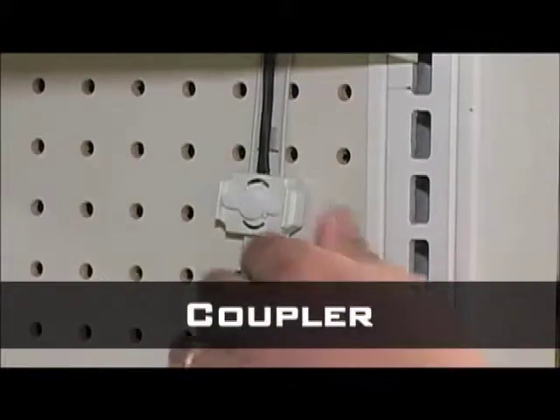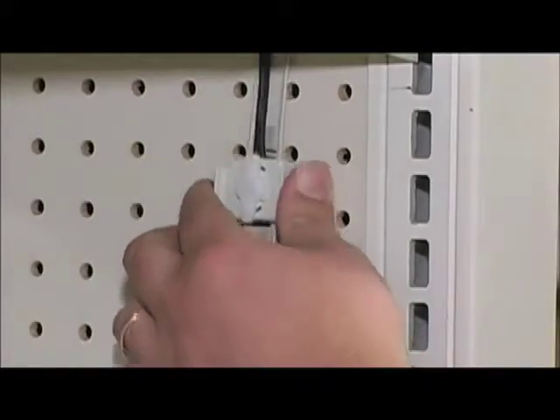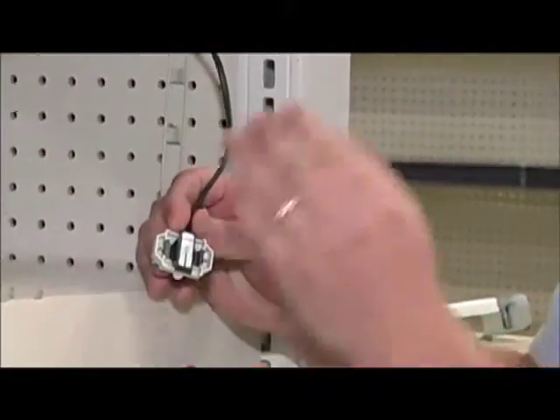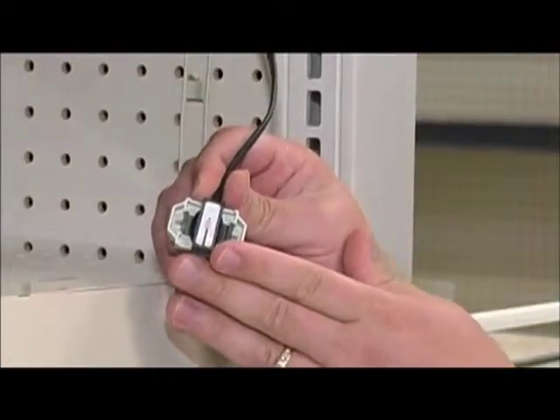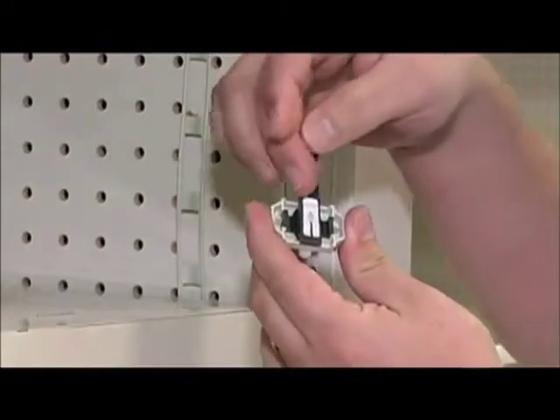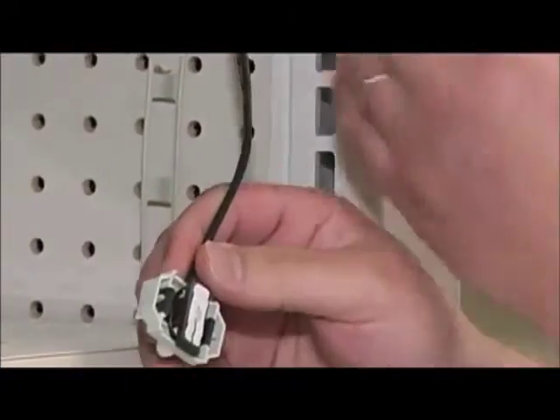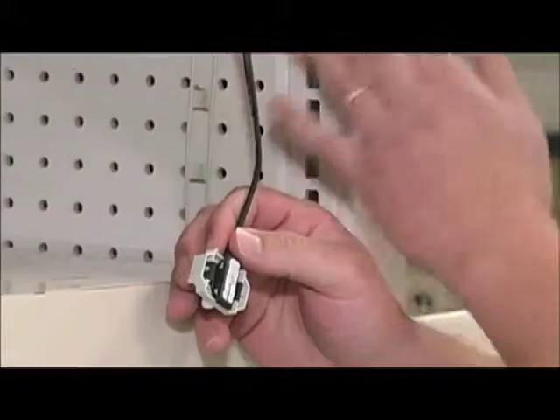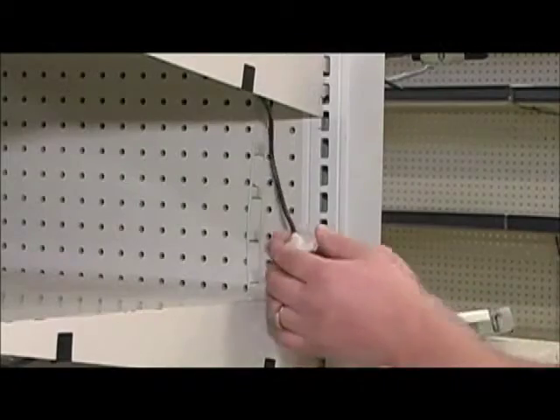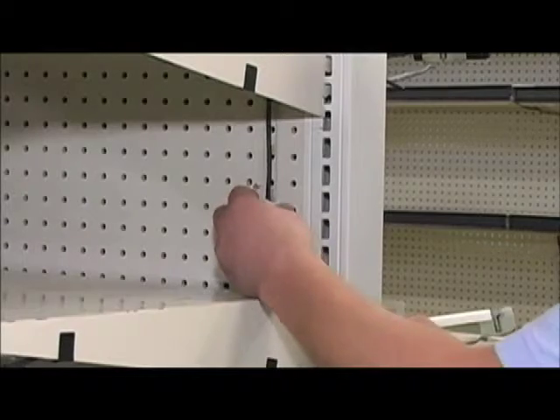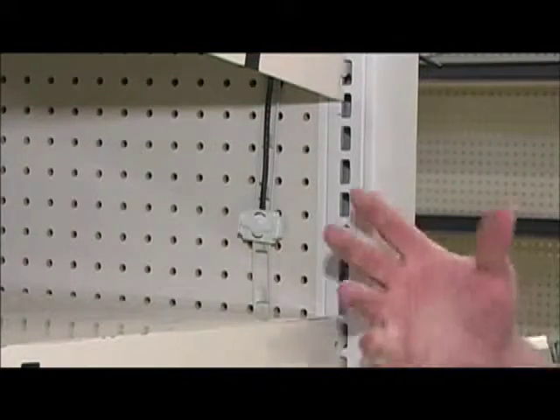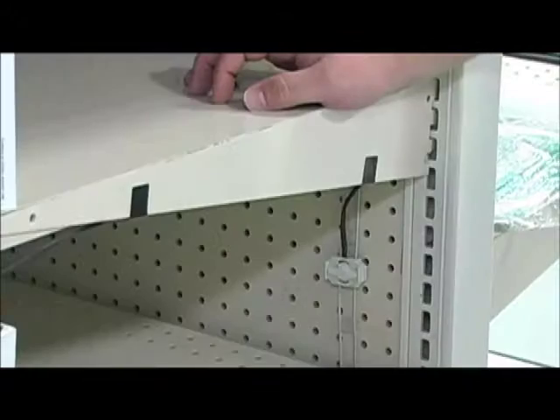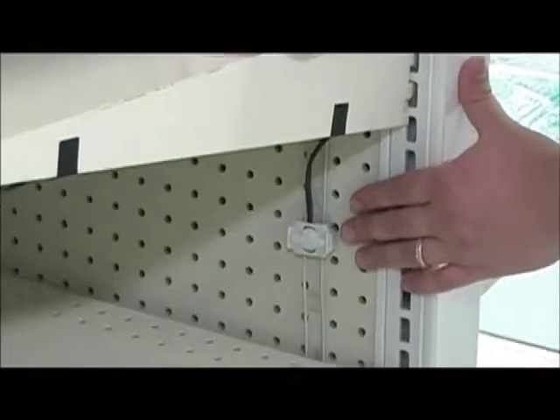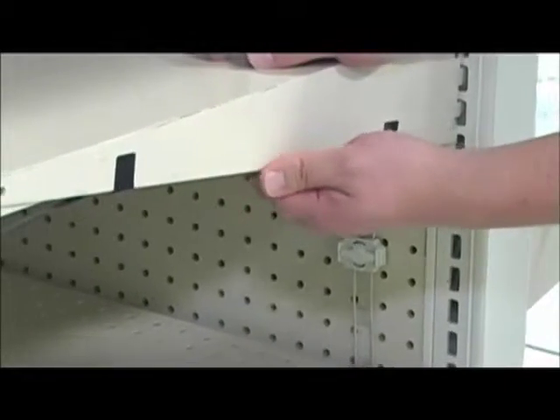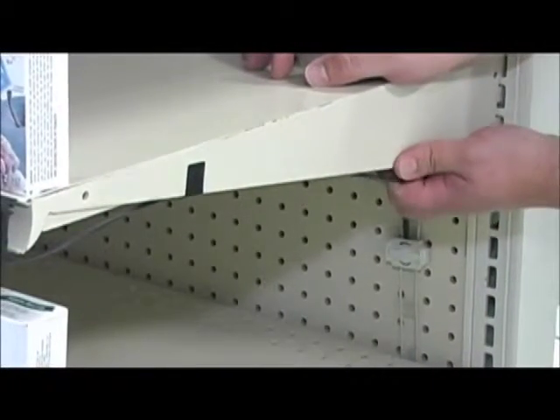The coupler is unique in that it has inductive coupling and allows power communications to travel from the riser to the coupler. The uniqueness of this is the ferrite core that excites the electromagnetic field generated and allows power communications to be transferred through the rail. The coupler can easily be removed or added for height adjustments of the shelf. Once the coupler is attached, power communications is distributed through the wire called a pigtail. The pigtail is attached to the side of the shelf and kept up through a pigtail clip.